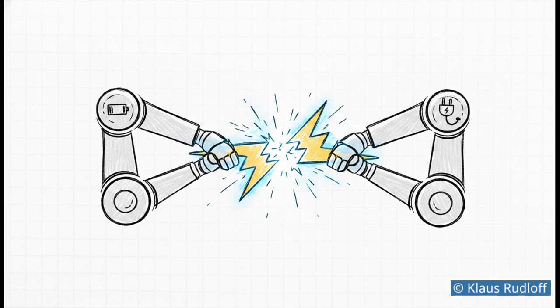And this doesn't happen slowly, by the way. This systemic tug-of-war can trigger severe reactions in a matter of milliseconds. Imagine one system aggressively trying to push the voltage up, while the other system misinterprets that push and immediately tries to pull it back down. The result? A highly unstable operational environment characterized by wild, rapid-fire corrections. It can severely threaten the integrity of utility-scale parks, turning what should be a robust energy storage facility into a volatile battleground of competing algorithms.